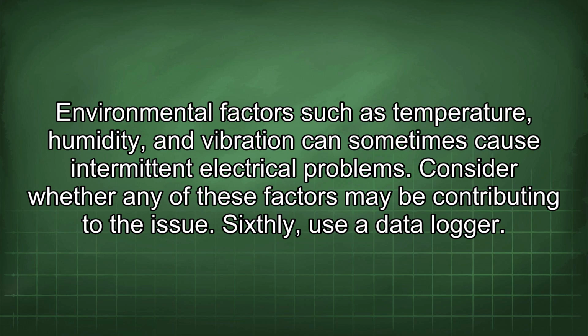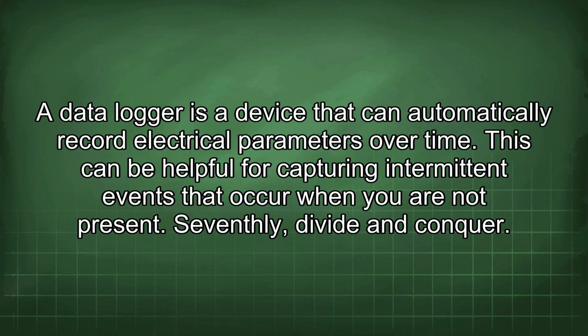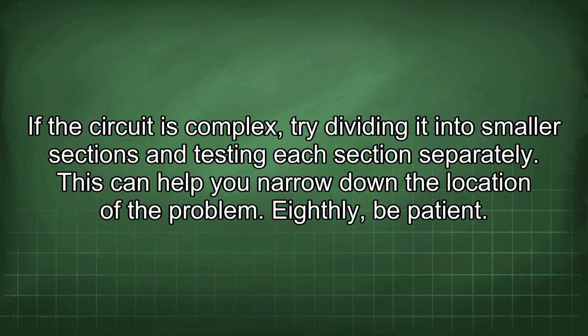Sixthly, use a data logger. A data logger is a device that can automatically record electrical parameters over time. This can be helpful for capturing intermittent events that occur when you are not present. Seventhly, divide and conquer. If the circuit is complex, try dividing it into smaller sections and testing each section separately. This can help you narrow down the location of the problem.